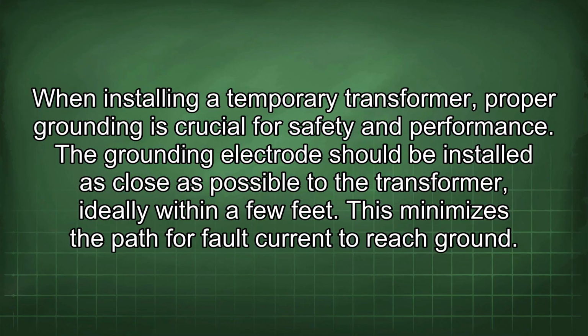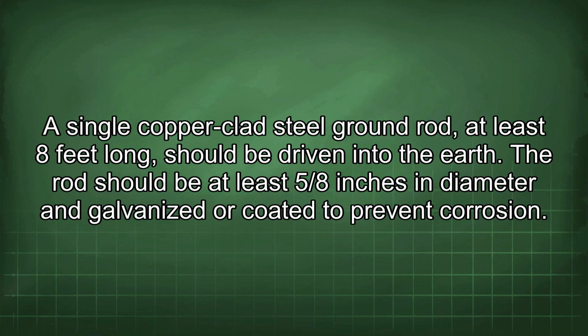When installing a temporary transformer, proper grounding is crucial for safety and performance. The grounding electrode should be installed as close as possible to the transformer, ideally within a few feet. This minimizes the path for fault current to reach ground. A single copper-clad steel ground rod, at least 8 feet long, should be driven into the earth. The rod should be at least 5/8 inches in diameter and galvanized or coated to prevent corrosion.